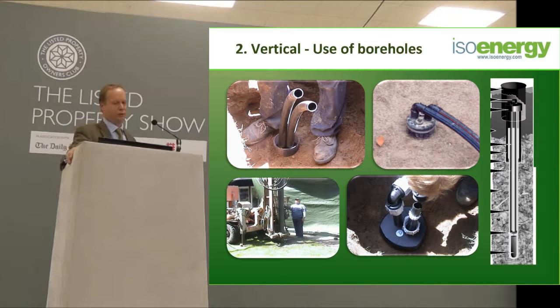For vertical boreholes, the same principle applies — don't put the boreholes only two metres apart, because you'll freeze a small area even though the problem now goes vertically. If you're not careful, you end up with a hundred-metre popsicle in the ground. There's no sun to warm the ground at a hundred metres depth, so it could take two years to recover.